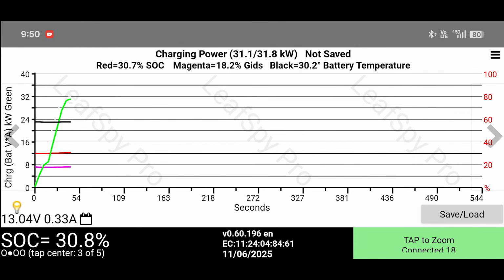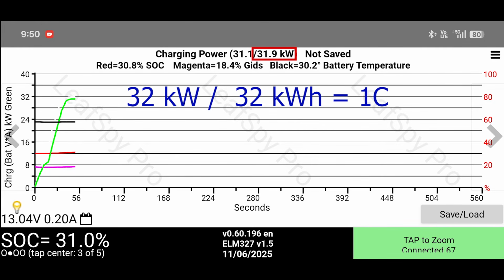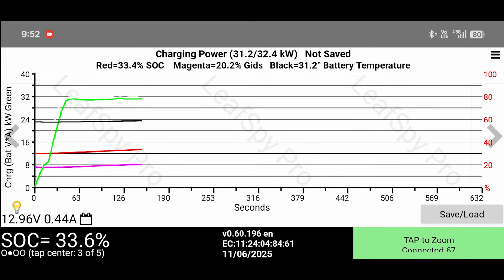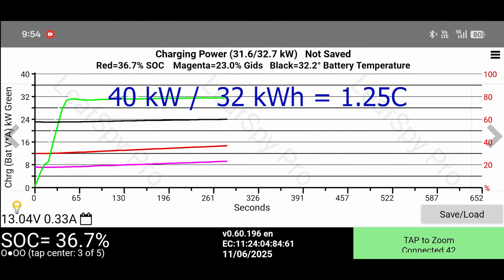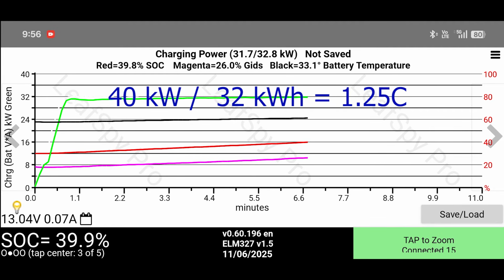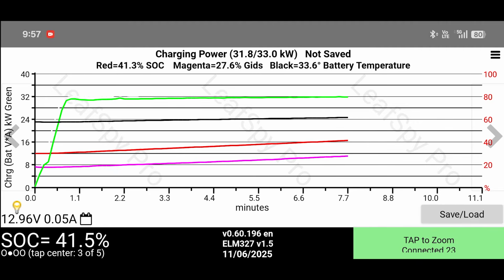So the charging power quickly ramps up to about 32 kilowatts, which is exactly a 1C charge rate, which is actually quite okay for this temperature. Without the limiter in place, it would have climbed up to 40 kilowatts, which is a 1.25C charging rate, which can certainly shoot the pack temperature up if allowed to persist for a longer period.